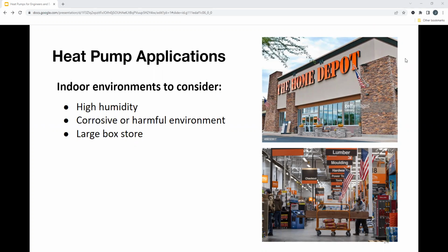One being high humidity. Right off the bat, VRF or heat pump technology is designed to be controlled to dry bulb temperature. It does not control humidity, and a lot of the controls, without any third party or large BMS systems, don't read humidity. So in a high humidity setting, let's say 80% or 85% relative humidity, that might not be the best application, because there's going to be a lot of sweating going on. That fan coil is going to be attacking a lot of the latent load and might not be able to produce the sensible load that it needs. So that's something to watch out for.